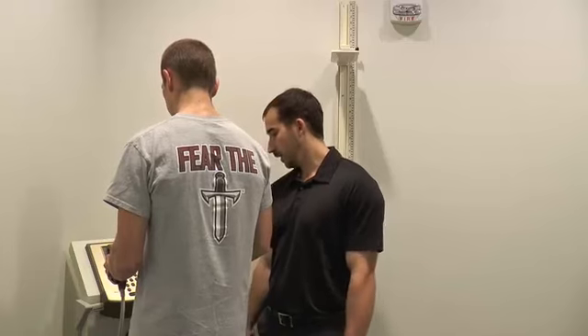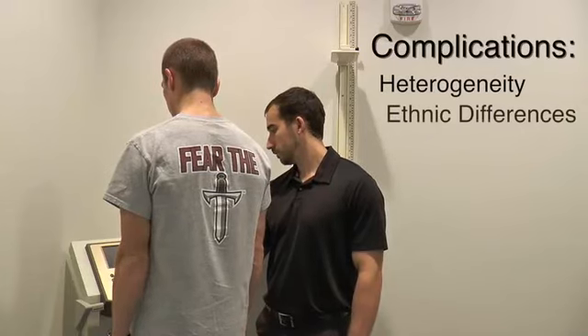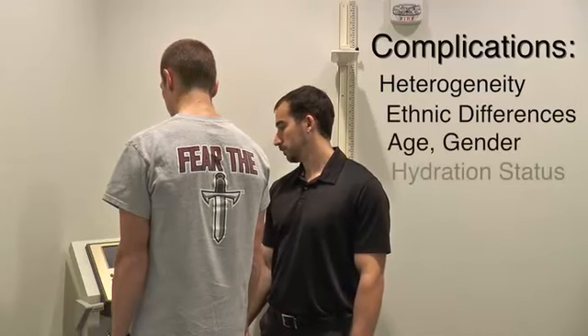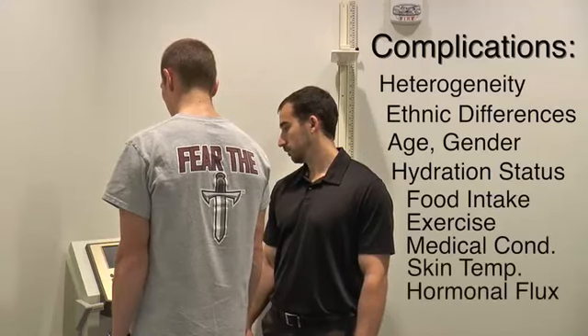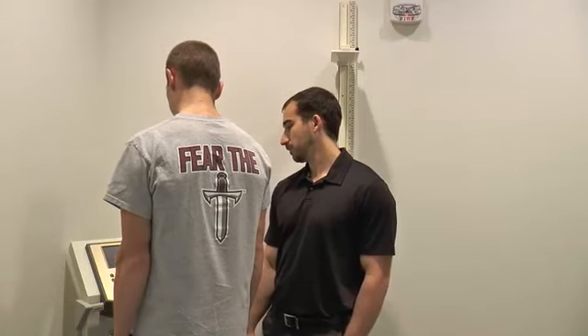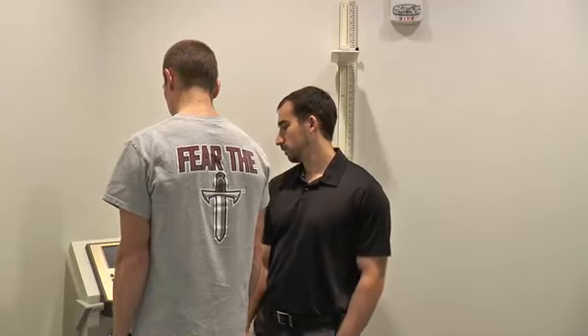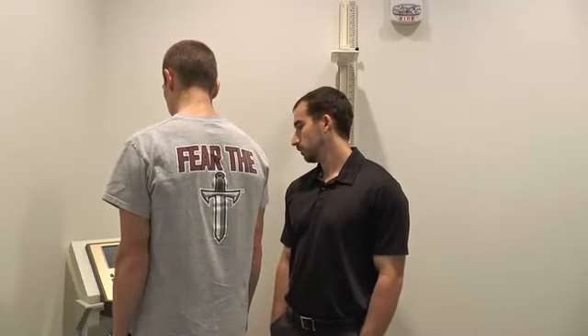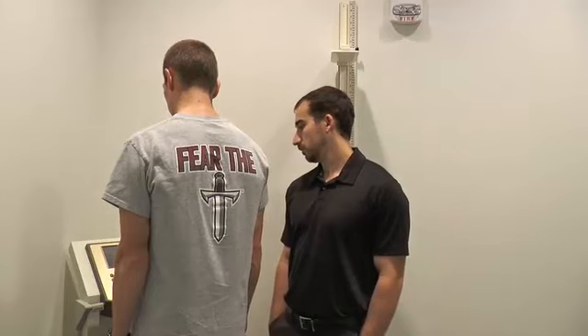However, BIA accuracy is complicated by many factors, including heterogeneity in body compartments and ionic composition, influence of ethnic differences in body composition, age, gender, hydration status, food intake, exercise, certain medical conditions, skin temperature, hormonal fluctuation, and fat distribution pattern. The equations are population-specific and may not apply to individual subjects or population subgroups. Some machines do include race as a factor in the predictive equation. Prior to the test, subjects must avoid alcohol and exercise. During the test, subjects must assume proper posture and have no metal objects such as belt buckles or coins in their pockets. Although this is a quick, relatively inexpensive field method for measuring body fat, it consistently overestimates lean people and underestimates obese people.